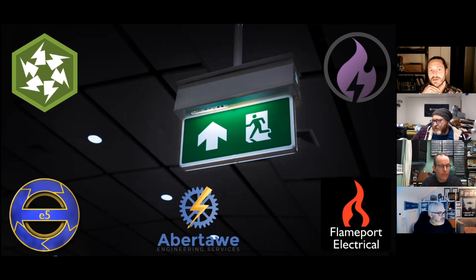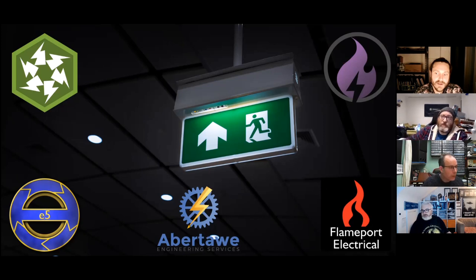Is that a recent change? Because Will's put in the chat, change in 2017, it was okay in 2013 but not now. Is that referring to this, where we want to keep them separate? Yeah, because it's about what one fault affects. It's an integrity issue again. So combining it all into one 4-core cable is probably not ideal, like we discussed earlier. Where we have a risk of impact or damage to one cable that then compromises 2 separate systems of sounding and detection, it's not as good for integrity as isolating just one loop. Okay. Right, Eddie Clements says, surely a manual call point is more important than also the C1.